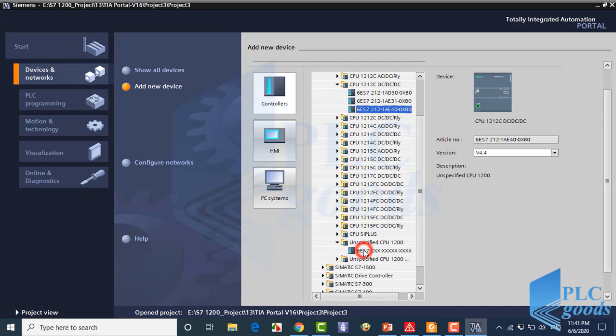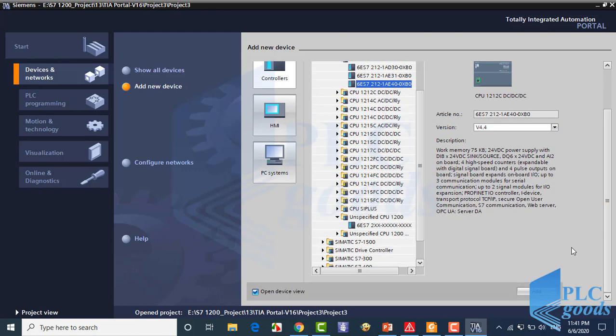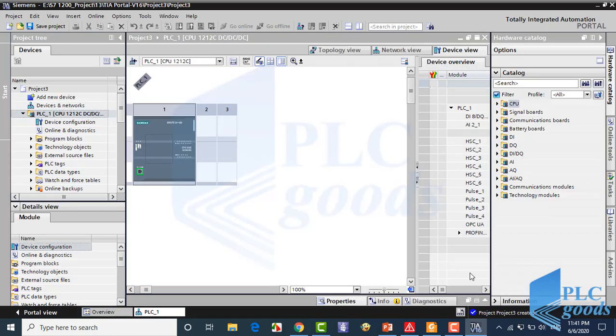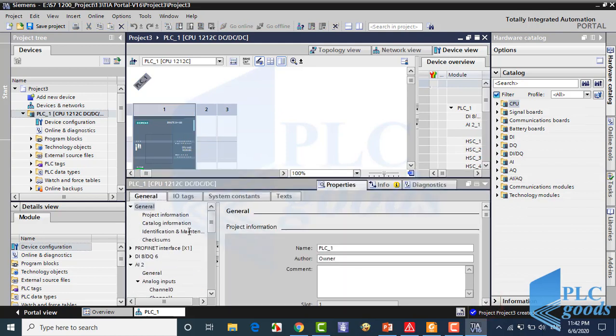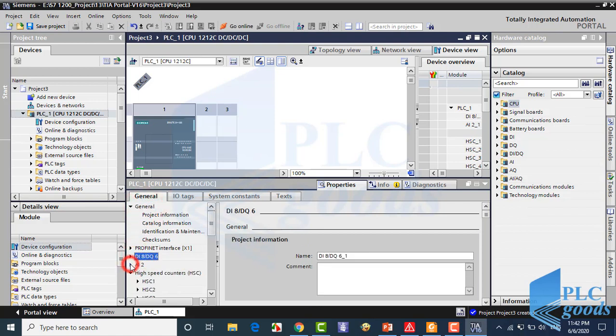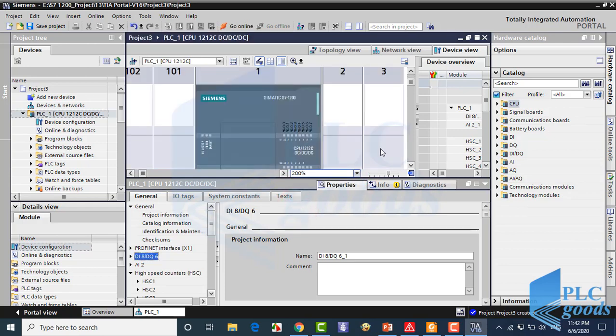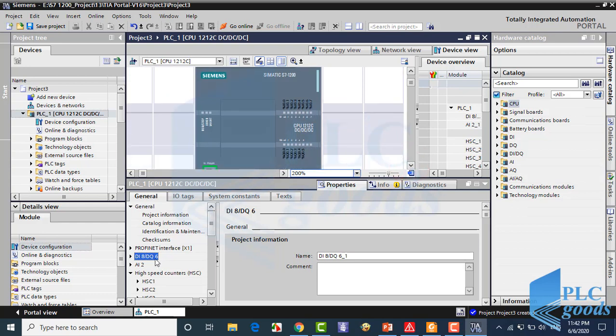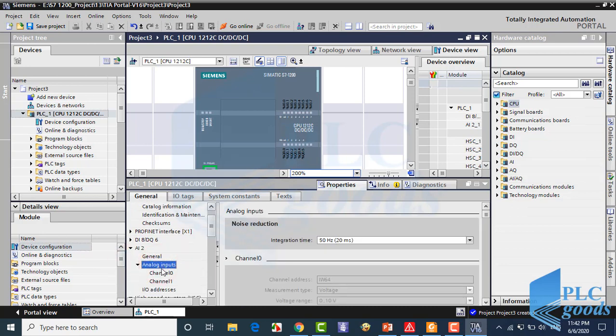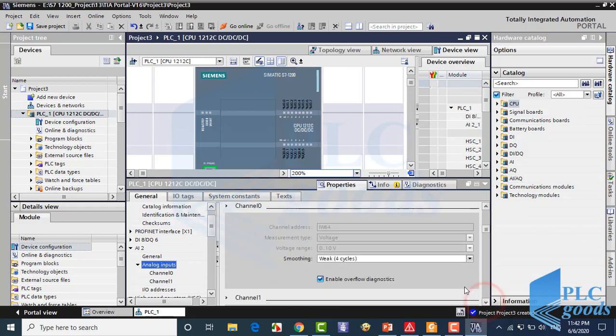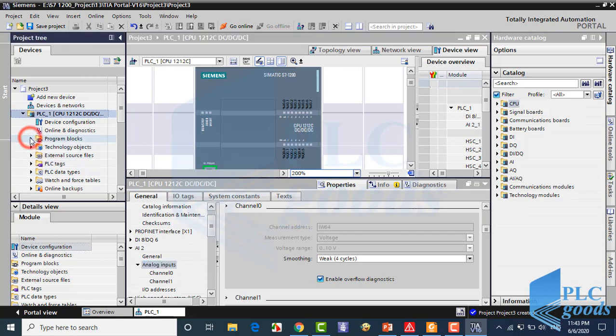You can select this item to determine your CPU later. Select your CPU to see its details in the bottom window. As you see, my CPU supports eight digital inputs, six digital outputs, and two analog inputs named channel 0 and channel 1. The address of channel 0 is IW64, so this channel uses 16 bits of PLC input memory. It only supports voltage signals from 0 to 10 volt. Now let's write a function to use this channel.